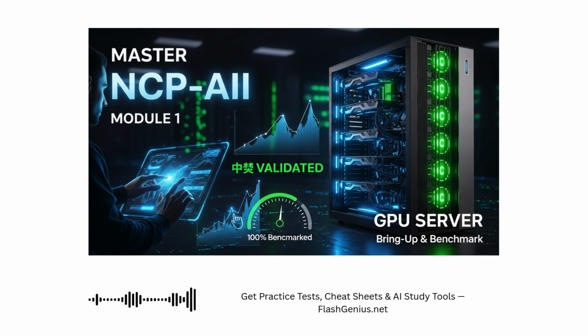All right, mini review 2, 4 points. First, your AI network topology has to be a symmetrical Clos or fat tree for non-blocking communication. Second, you have to segment your network traffic, dedicated RDMA for training, and separate networks for storage and secure OOB management. Third, your cabling choice depends strictly on distance. DACs for short, AOCs or fiber for longer. And you have to validate the links for full speed and low error counts. And fourth, power validation means testing PSU redundancy. Cooling validation means running stress tests and confirming temps are stable and well below throttle points.